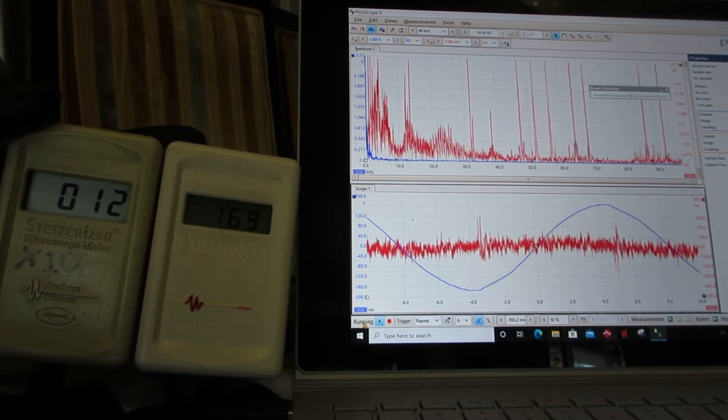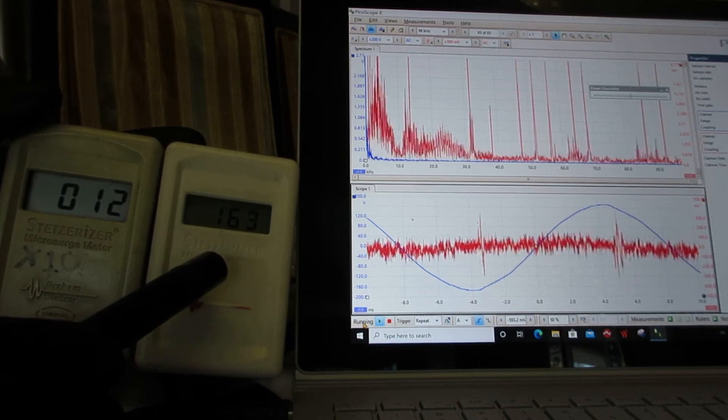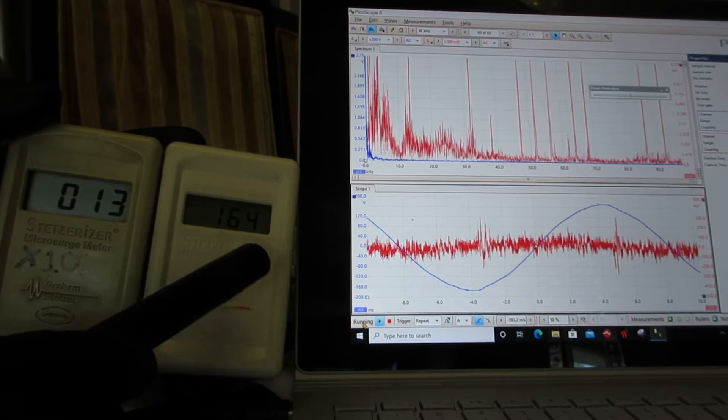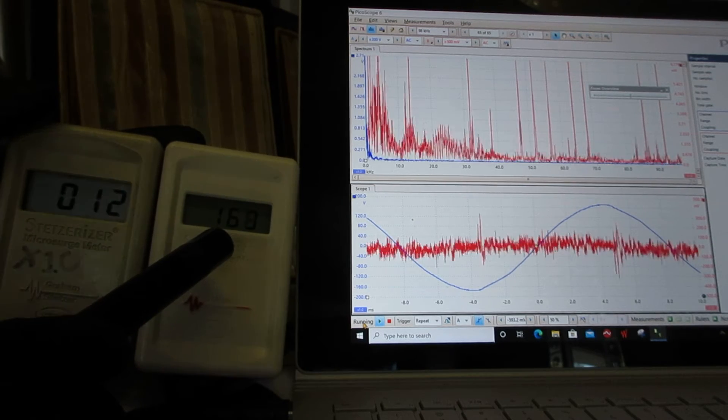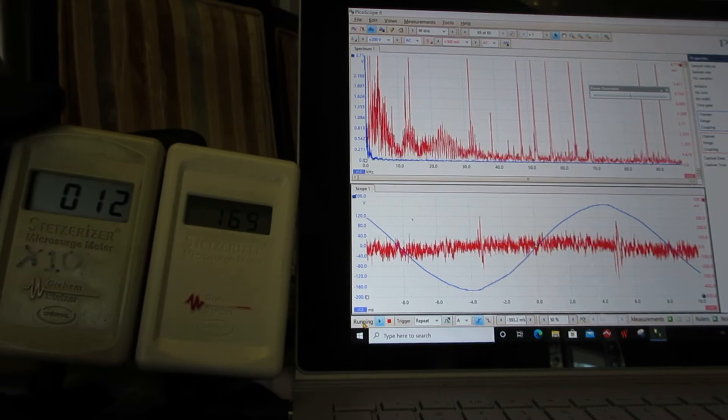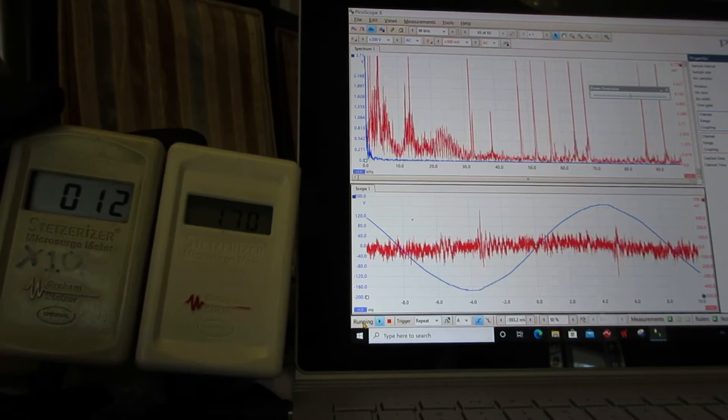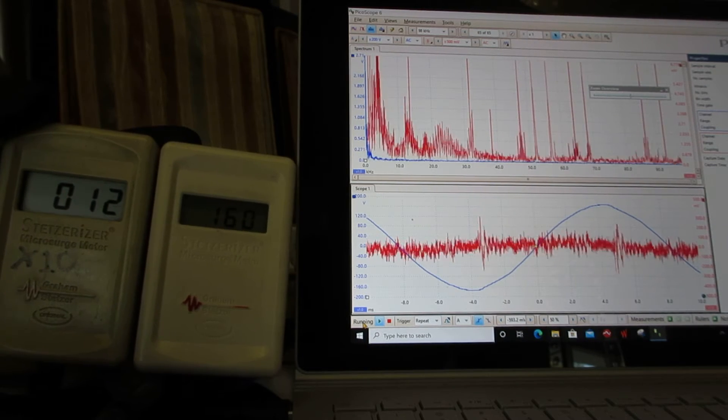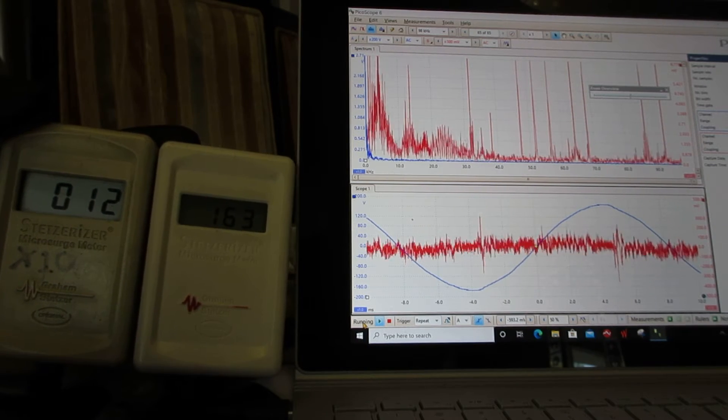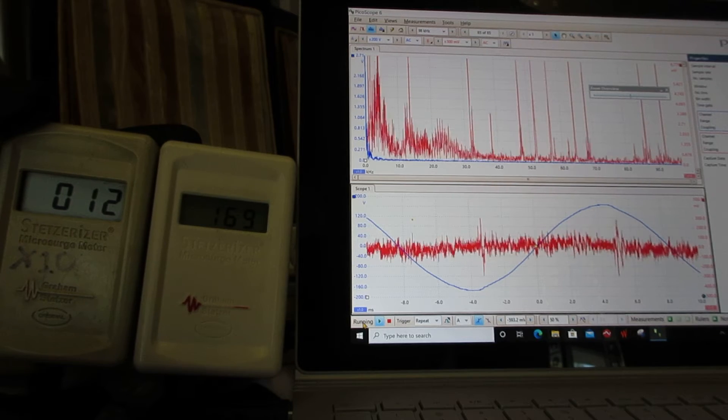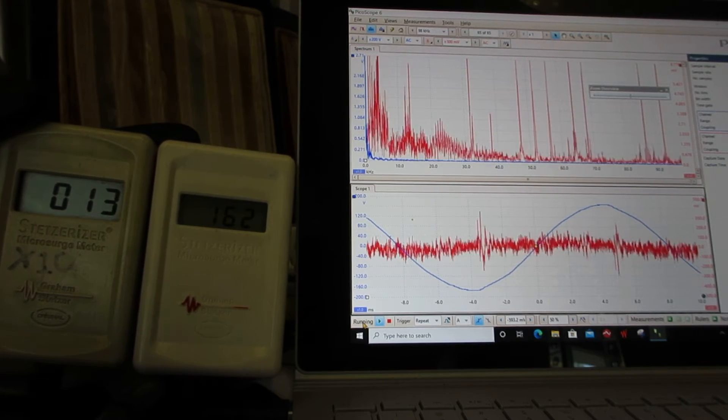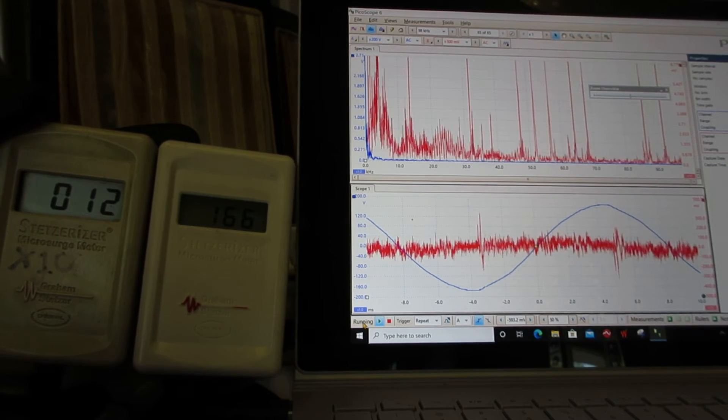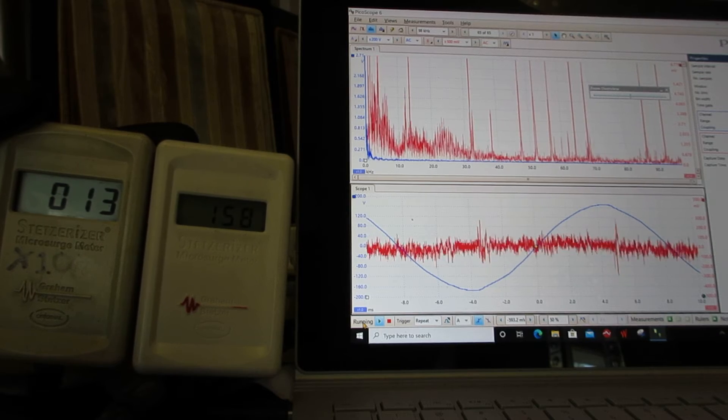So it's off, right? Yes. Instantly we saw a drop from 8,800 down to 160. So it's related to the solar. I suspect one or more of the microinverters is failing because normally Enphase is a very clean brand.